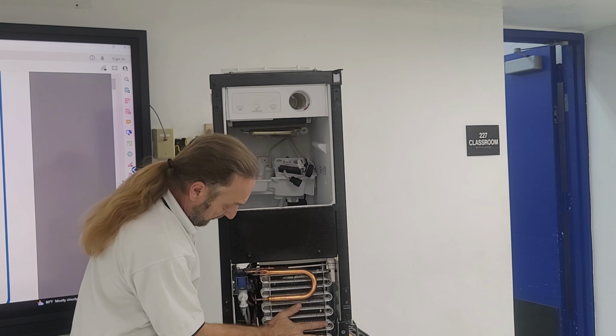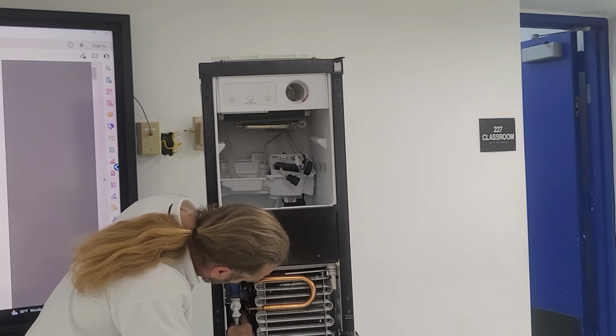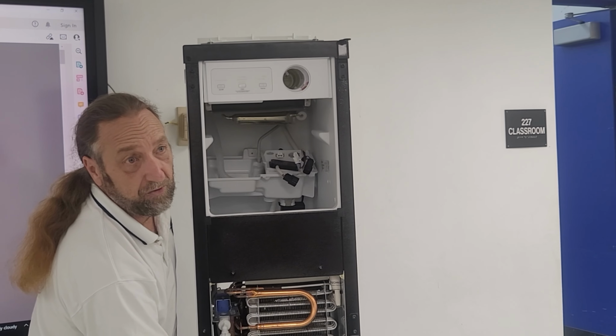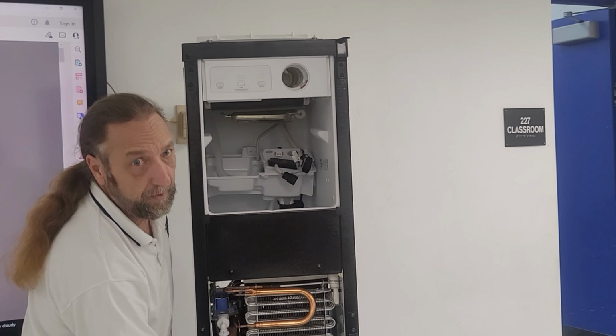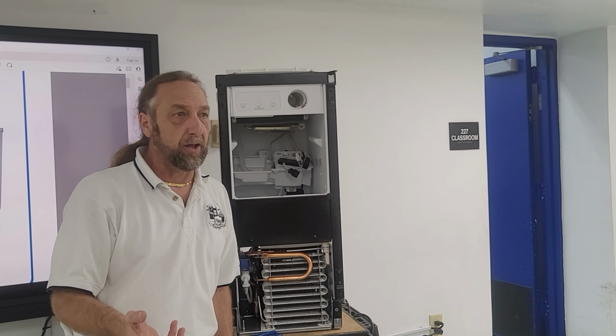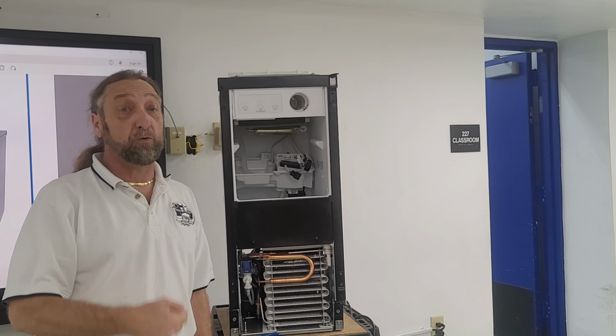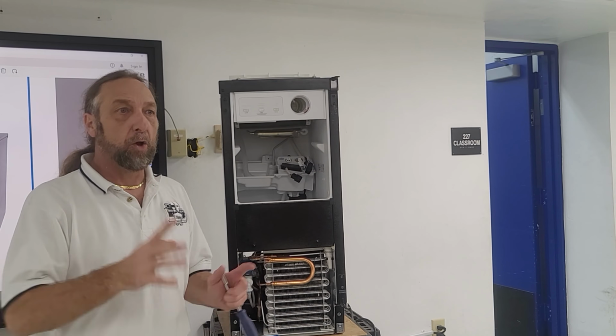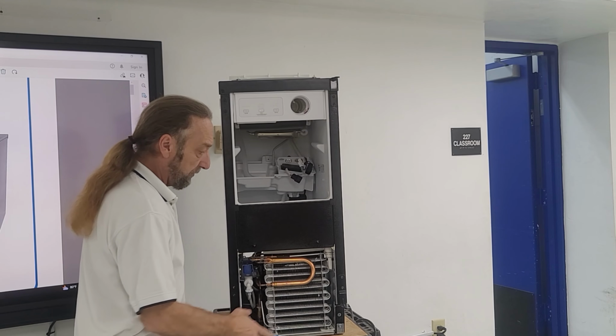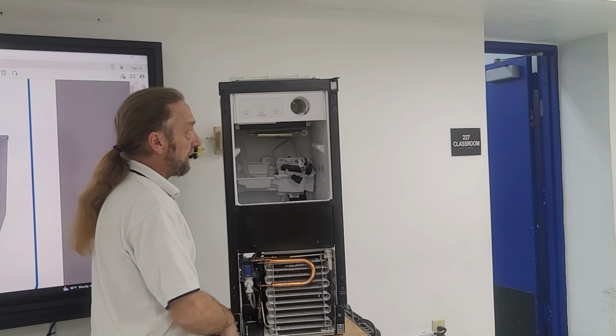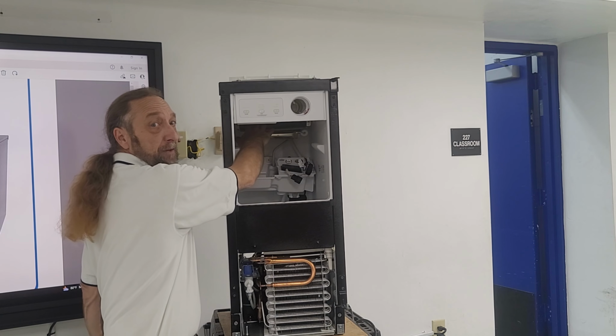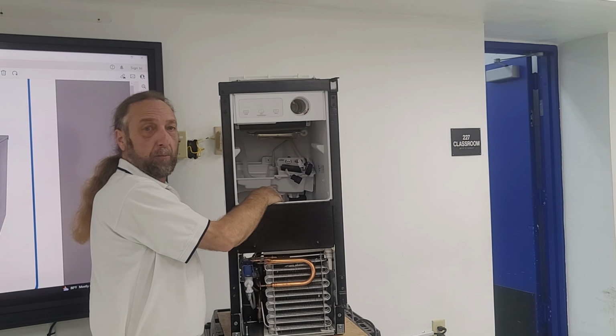So this is our condenser here. This is our water valve. It's a little hard to see here, but there's something called a hot gas valve. That hot gas valve is a solenoid that controls the flow of the refrigerant. Normally when a refrigerator runs, the compressor pumps into the condenser. Condenser goes through a cap tube up to the evaporator, and it comes back to the compressor.